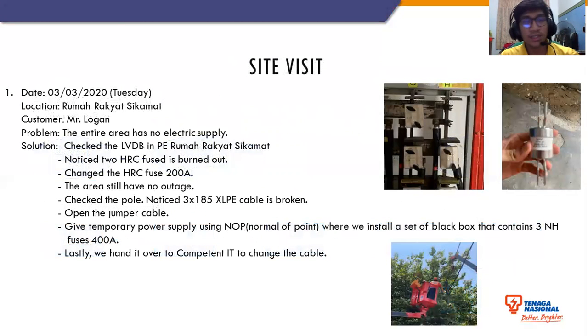Okay, on the site visits, I went to many, therefore I only focus on three. The first one is at the Rumah Rakyat Sikamat. The problem is the entire area has no electric supply. Therefore, we checked the low voltage distribution board in the electrical substation at Rumah Rakyat Sikamat. We noticed 2 HRC fuses had burned out.